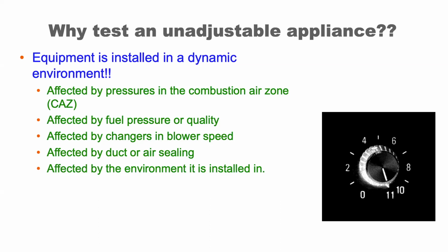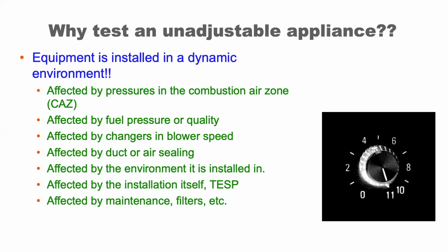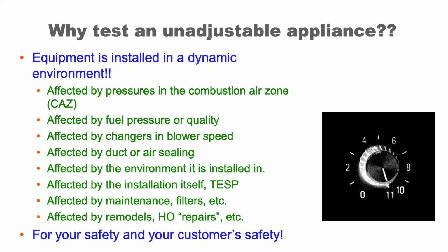And affected by things in the environment it's installed in, chemicals, anything that happens to be in the air that's not supposed to be in the air that can get in and be changed chemically in the combustion system. And also by the installation itself, the pressure, the total external static pressure, which can change the way the air flows. And that gets back to sort of the same idea as the concept of the blower speed changing. And maintenance, filters, again, affecting the airflow. We're talking warm air heat exchangers and heat being taken away at the correct rate, the designed rate. And also by remodels of the space, of the ductwork, of even the equipment, or homeowners attempting to do repairs on equipment. All these things can change. And that's why it's a good idea to test all the systems like some of the people are, and they're shown in the poll.